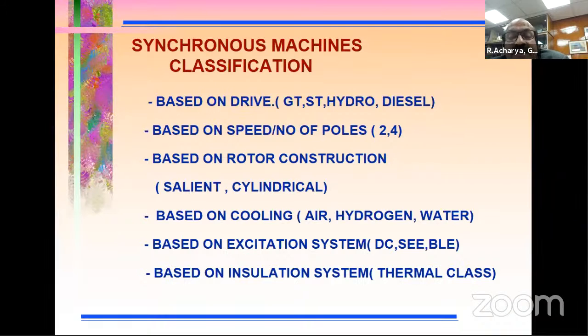Based on rotor construction, it can be salient or cylindrical. Based on cooling, as I've already mentioned, hydrogen, air, or water cooling systems are normally used, basically for large capacity machines - like the 2200 MVA I mentioned, where both stator and rotor are water cooled machines.